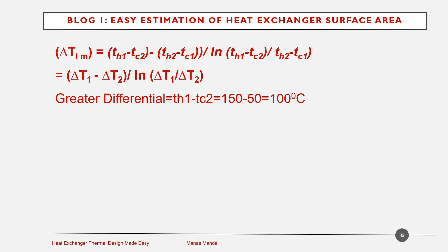Now we have to calculate the log mean temperature differential, LMTD. How is it calculated? Already we have seen TH1 minus TC2 is the greater differential, hot medium temperature minus cold medium outlet temperature. So TH1 minus TC2 will give us 150 minus 50, 100 degrees C. The smaller differential, as we have seen in the earlier graph, is TH2 minus TC1, equals 100 minus 30, equals 70.